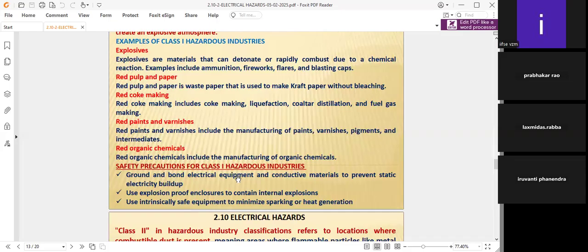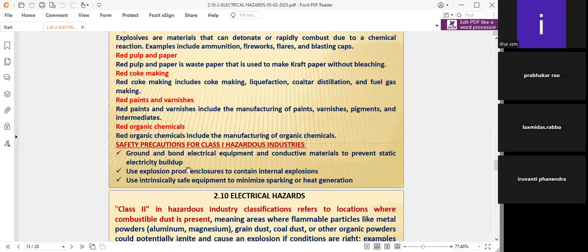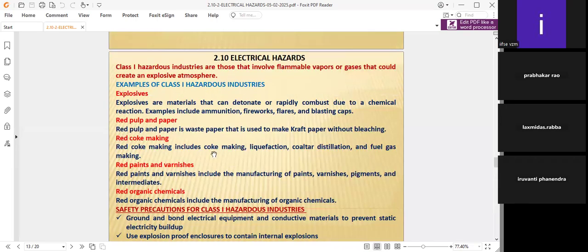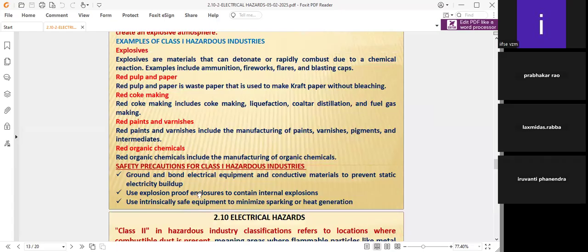Normally, we are discussing these things only for hazardous area operations. In hazardous area operations and industries, electrical equipment is taken much more care of, including the earth, the circuit, the earthing, the fuses, the ELCBs, and the RCDs. We take much more care in red category industries, or class 1 hazardous area industries. Use explosion-proof enclosures, because the explosion will be contained within the enclosure itself. We have to provide some facility so that any internal explosion is taken care of where abnormal conditions are there.